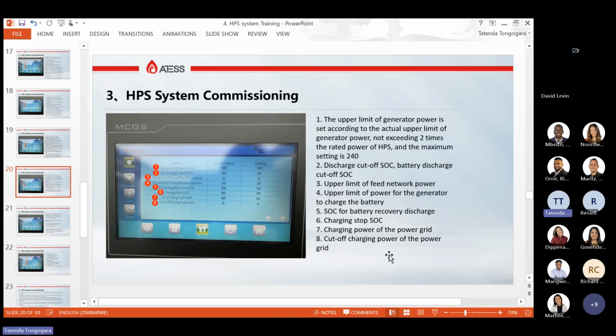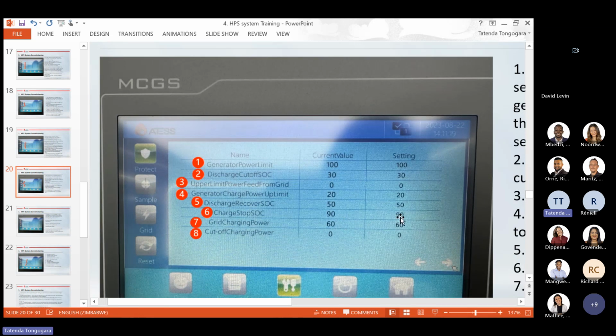And on the new firmwares, we now have the cutoff charging power of grid. If you want to charge with the grid, you can set at what SOC your system should stop charging with grid. So if you set it to 80%, it will stop charging with grid at 80%. And then we have number 6, which is charge stop SOC. This one you have to set from 95 to 100. For some batteries, it's 100. So if during installation and commissioning you run your system and it stops charging at maybe 50%, you need to check this value. Is it set to 100? For this client, it was set to 90 and it just stopped charging at 90%. Why is my battery not going above 90%? Just verify this value.